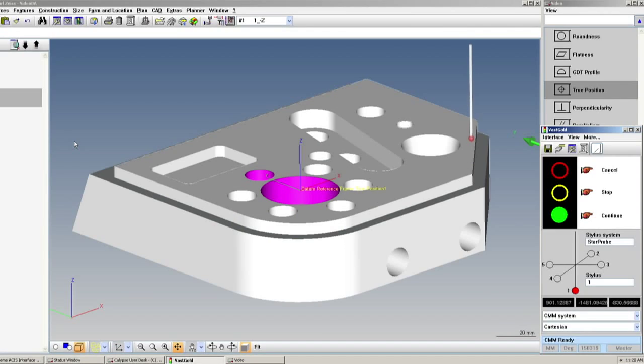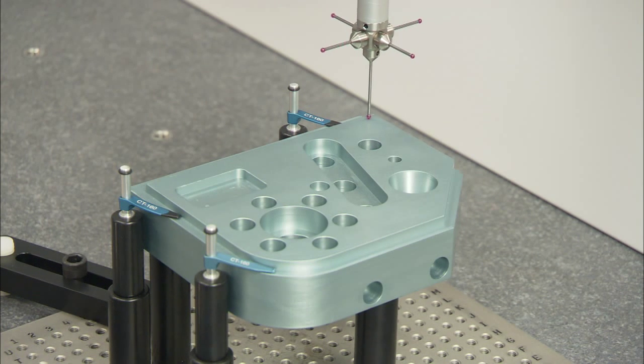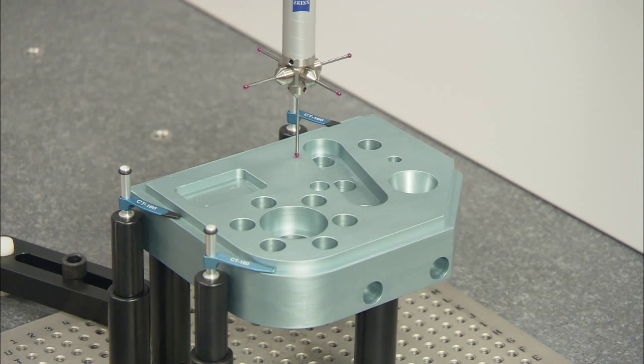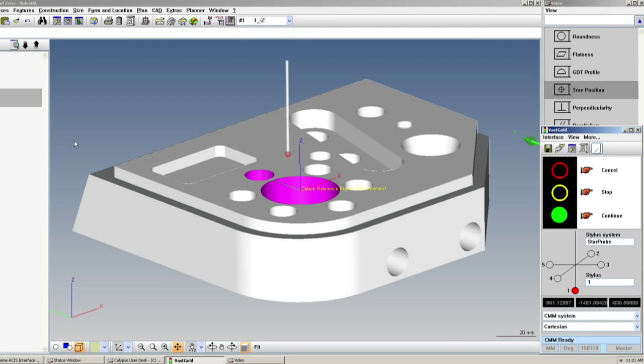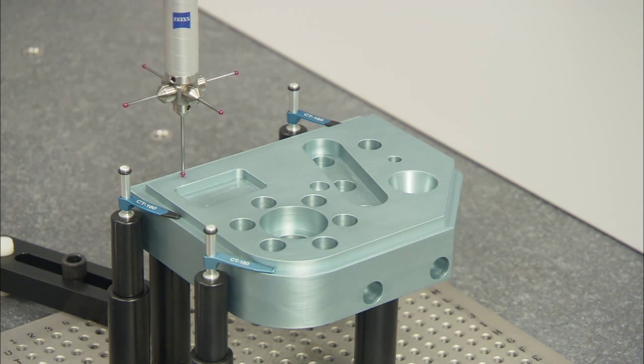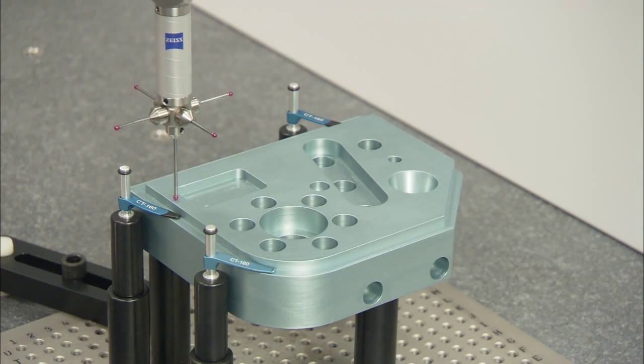When you input your parts and set up the desired characteristics, Calypso takes care of many of the details for you. Based on the aspect being measured and the type of feature, it recommends optimal settings for probe speed and data density. This saves time and assures reliable results.